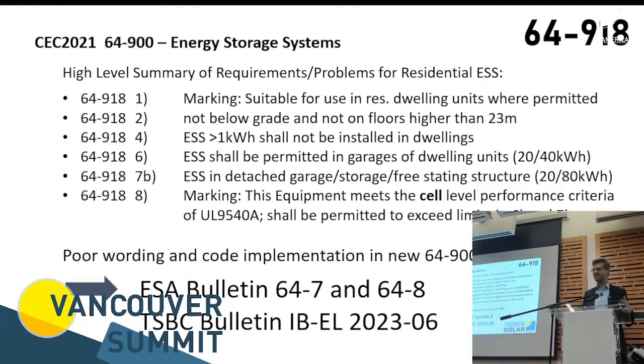So 1 kilowatt hour is extremely small, so that's pretty useless for a stationary system. It's fine for your UPS system, for your router and your internet and whatnot, because that's typically a few hundred watt hours. But for a real battery backup system or grid-tied energy storage system, you typically talk about 10, 15, 20 kilowatt hours for the average household. So it's saying it can't be more than 1 kilowatt hour? That's what the code says. And that doesn't make any sense. Exactly. But that's what's written right now, and that's where it's so difficult. And we will talk about what the options are in BC or in Ontario with those deviation options to still install battery storage systems in dwellings.